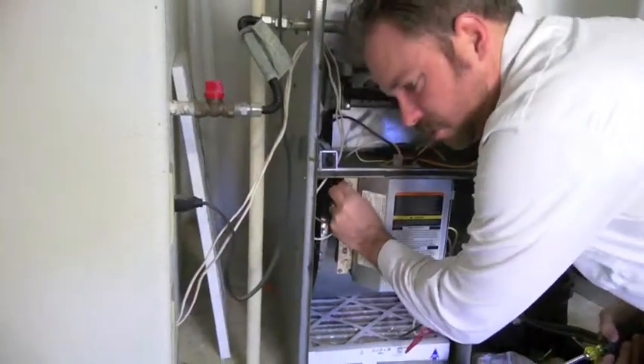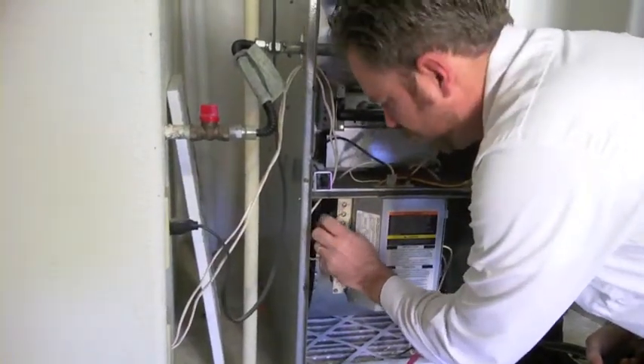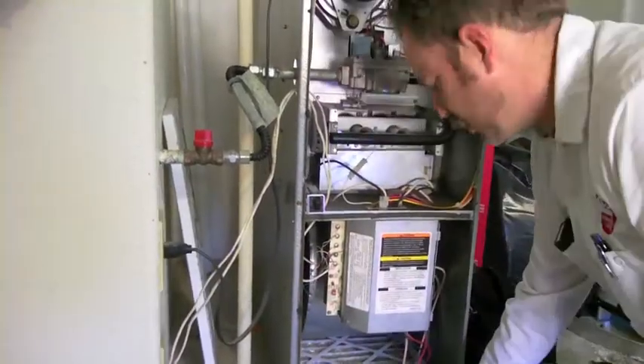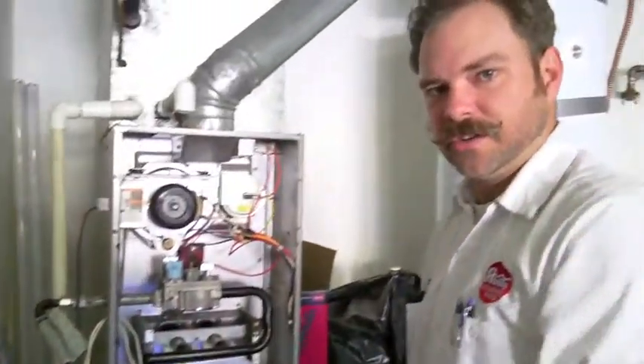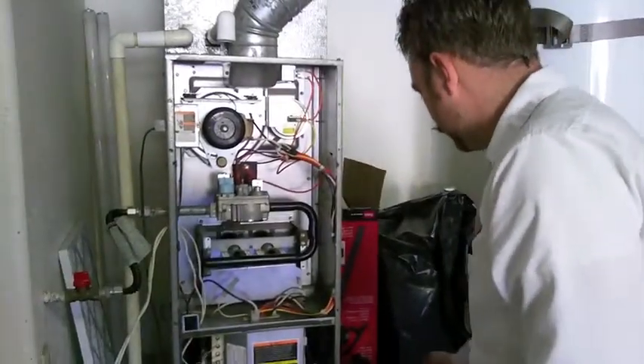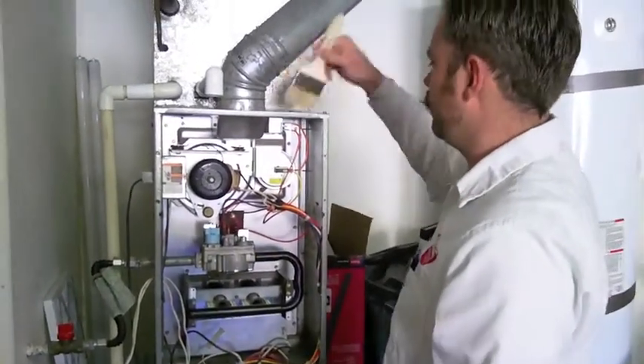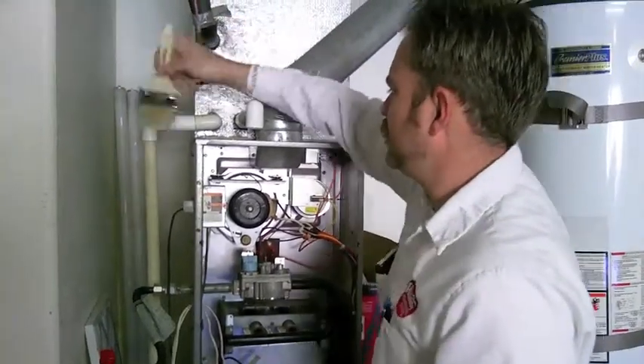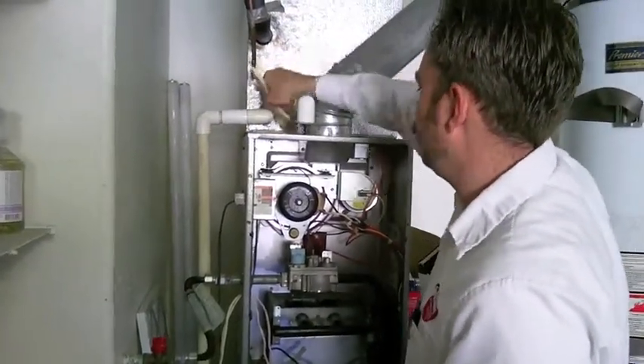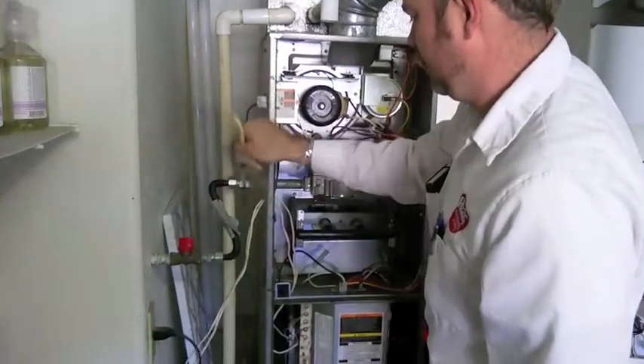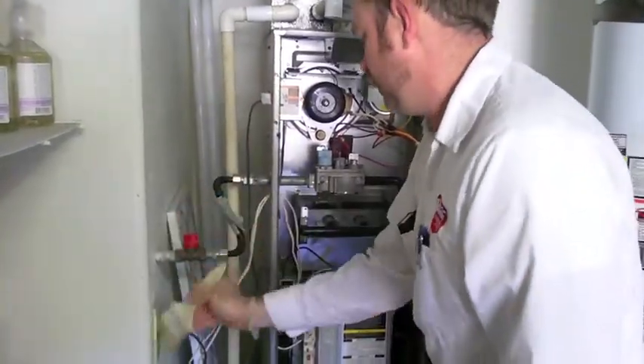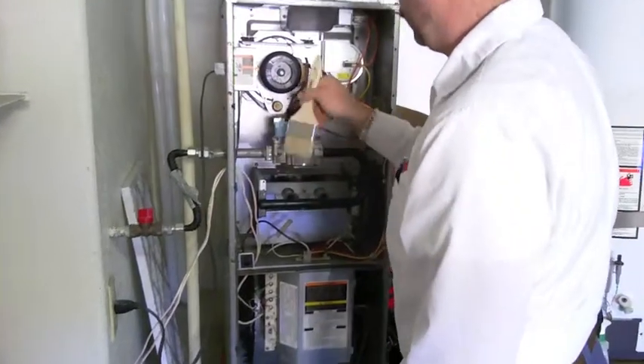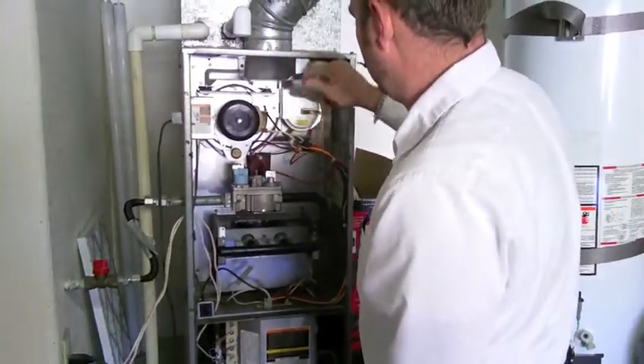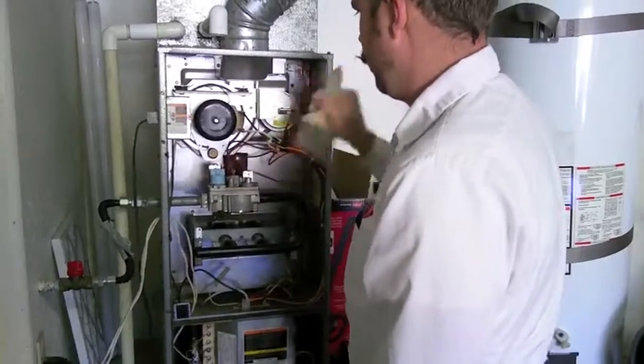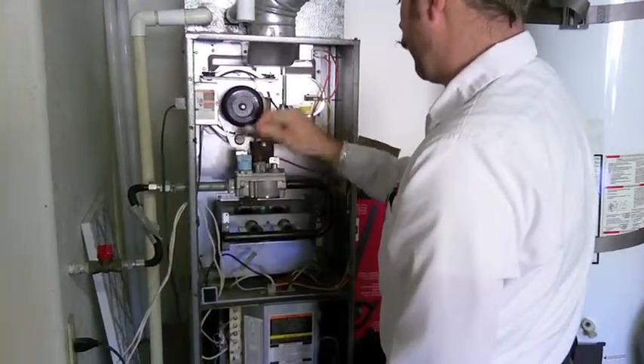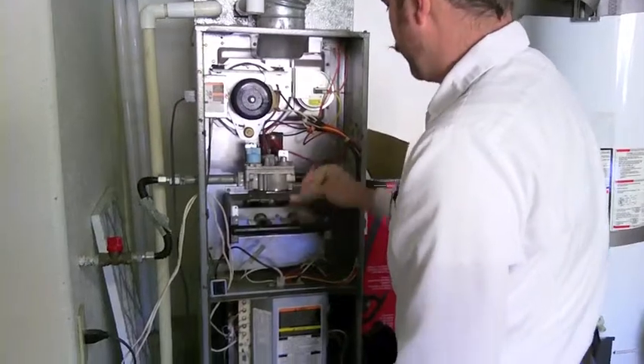First thing I'm going to do is just remove the heating wire, which is a W wire. Make sure that nobody can turn on the thermostat inside and turn this furnace on me. The second thing I'm going to do is start cleaning it up. So I take my brush and I just clean off all the dust. I try to go from the top and I brush all the dust down. That way it's all gone when I'm done.